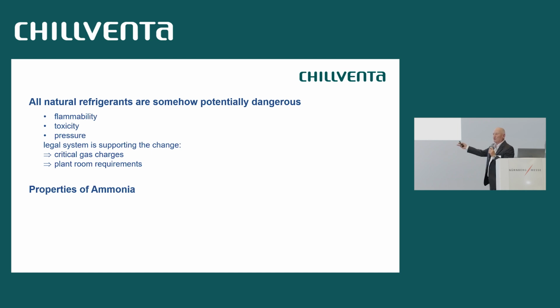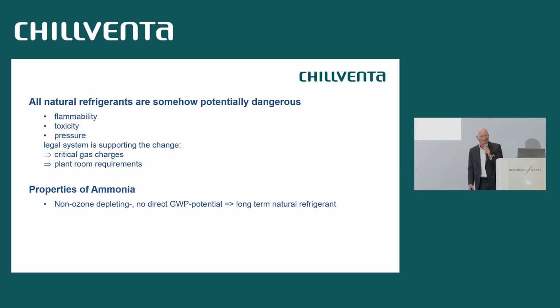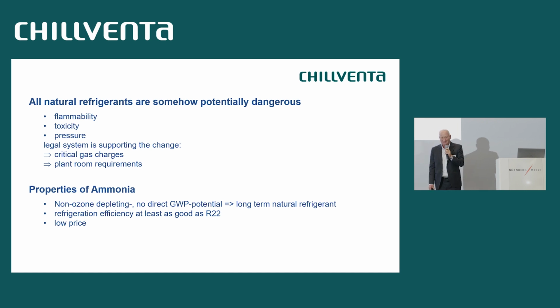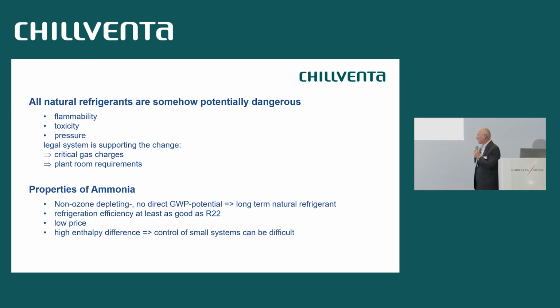Of course, it is clear I like ammonia. The properties of ammonia are very obvious. It's non-ozone depleting. It has no direct global warming potential impact. It's a long-term natural refrigerant, and it has got a refrigeration efficiency, which is as good as R-22. Last but not least, the chemical companies will not like to hear that, but it comes with a low price. The only downside I see is the high enthalpy difference makes it a bit difficult to control when we talk about low capacity systems.